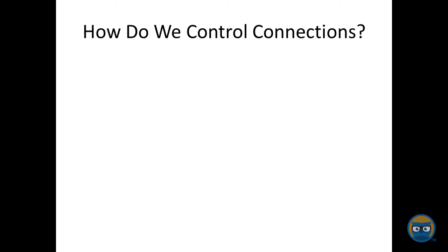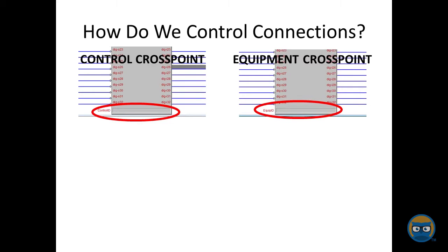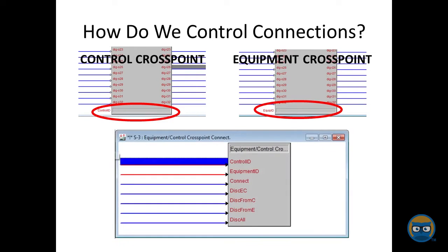Before we can pass any signals between a controller and an equipment, we have to manage connections between the two. Every control crosspoint has its own control ID and every equipment crosspoint has its own equipment ID, and these uniquely identify any equipment or control crosspoint in the entire program. To connect a controller to equipment, you put the control ID into the connector, you put the equipment ID into the connector, you pick how or if you want to disconnect any existing connections, and then finally you set the connect input high. A connection is made between the specified IDs once that connect input goes high.